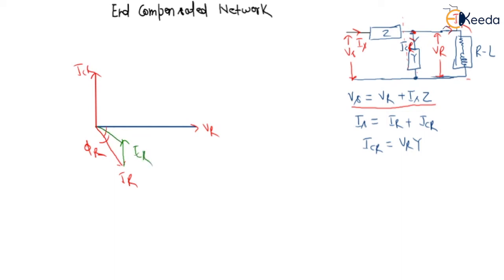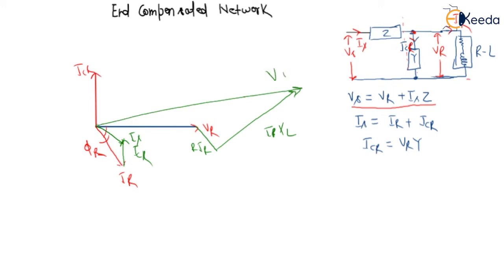Adding IR and ICR gives us IS. Now with IS, we can calculate VS: VS equals VR plus IS times R plus IS times XL. Adding these components gives us VS on the phasor diagram. The angle between IS and VS is the sending end power factor angle. The power loss is P_loss = 3 × IS² × R.